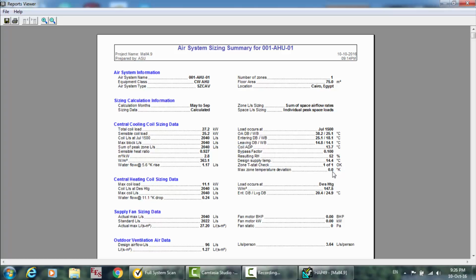This means that the temperature inside the zone will increase up to 25.8. Remember that we do not want this, but according to the psychrometric process, it depends on the internal loads and the environment of this zone and SHR. It depends on many things that may make the throttling range hard to get. So HAP will get more than this by 0.8. To sum up, here there is no problem, and the maximum temperature you will get inside the room will be 24 plus 1 degree, as we did in the throttling range.